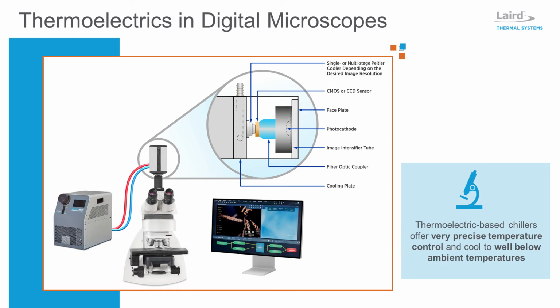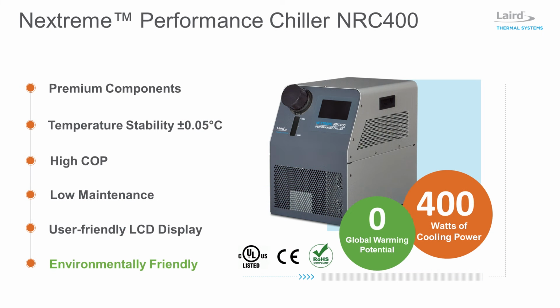A thermoelectric cooler is soldered to a cold plate inside the camera to further cool down the CCD or CMOS sensor housing to minus 20 or minus 30 degrees C, depending on the required image resolution. A recirculating chiller can be designed to cool other critical optoelectronic components, such as detectors and FPGAs. Laird Thermal Systems' Nextreme NRC400 Thermoelectric Chiller delivers precise temperature control stability to within plus or minus 0.05 degrees C under steady-state conditions for modern microscopy equipment.